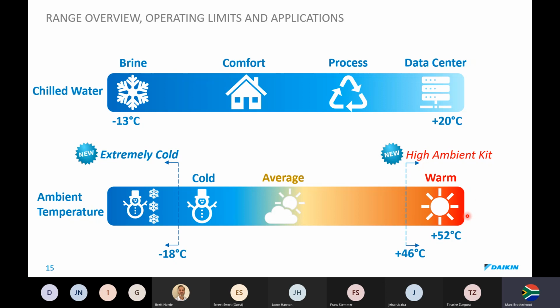So this would not really apply to the South African market, 52 degrees. These chillers will still be able to condense at 46 degree ambient, which is very unlikely that you're going to get those high temperatures. But in extreme situations, we can put a high ambient kit on, and you'll still be able to condense at 52 degrees. And here as well, for process cooling, even if the outside temperature drops to minus 10, you will still be able to condense and provide your cooling for your data centers or whatever your process may be.